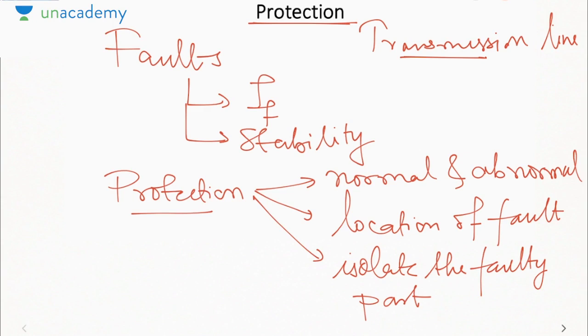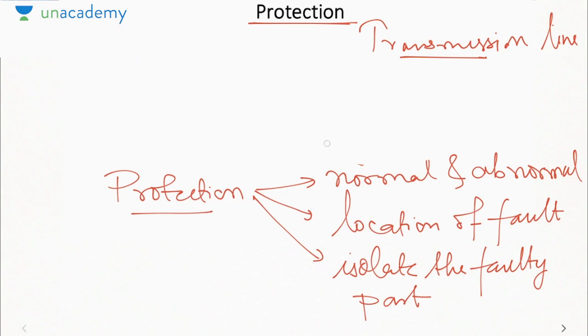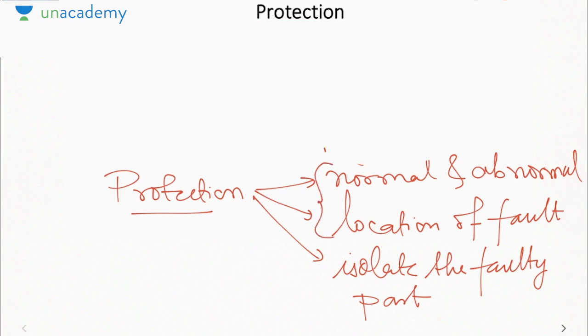Now, what are the parts of a protection system? As we see from the functionality, the first function is to identify between the normal and the abnormal condition. Now, these two steps, location of the fault and normal and abnormal, are done by relays, also called protective relays. Why? Because in general terms, a relay is nothing but an electromechanical switch. What is meant by electromechanical switch? That is, for an electrical signal, it will produce a mechanical output, just like the motor.